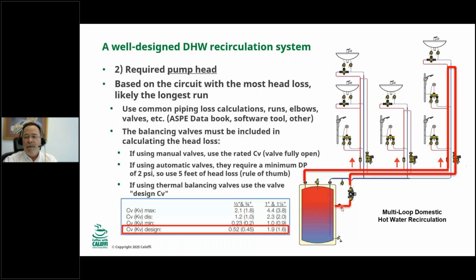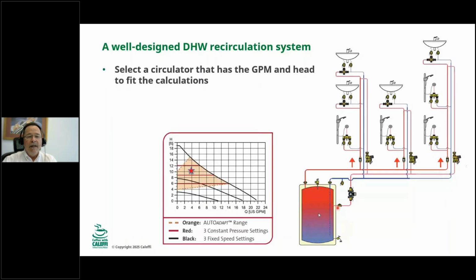So when you do that, let's just say, for example, that you came up with 4 GPM for that circuit and a total head loss of 10 feet. Then you use a pump curve like this, and you have to find a pump where your flow and your head are in the working range of that circulator. And I don't know if Bob or Max want to say anything about this. I'm not a circulator expert, but this is what you want. You want to be able to have that work in the range that you've calculated.